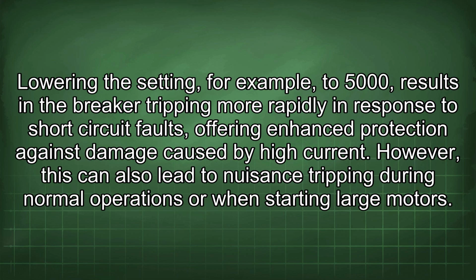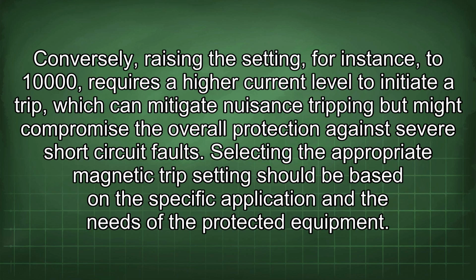Lowering the setting, for example, to 5,000, results in the breaker tripping more rapidly in response to short circuit faults, offering enhanced protection against damage caused by high current. However, this can also lead to nuisance tripping during normal operations or when starting large motors. Conversely, raising the setting, for instance, to 10,000 requires a higher current level to initiate a trip, which can mitigate nuisance tripping but might compromise the overall protection against severe short-circuit faults.